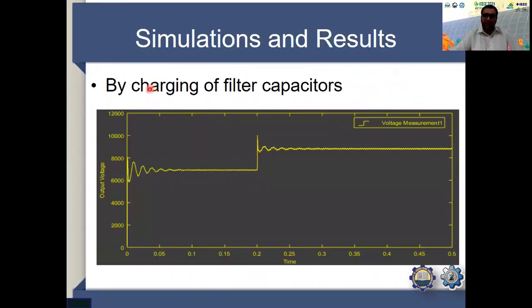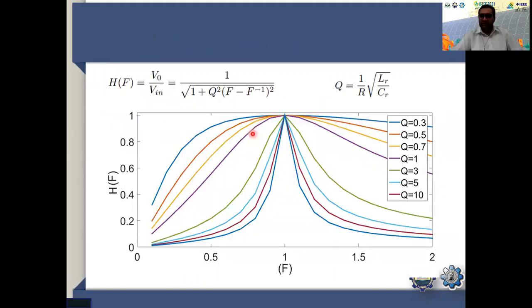When the input filters were charged up to their maximum value of 540 volt, we can see that the surges have reduced to a very respectable amount, but still such a response will not be acceptable for the magnetron, being a very sensitive load. This surge is still violating the limit of plus minus 200 volt. Even though this is for a very short time, it will damage the magnetron. So we came up with a solution that we have to implement a controller.